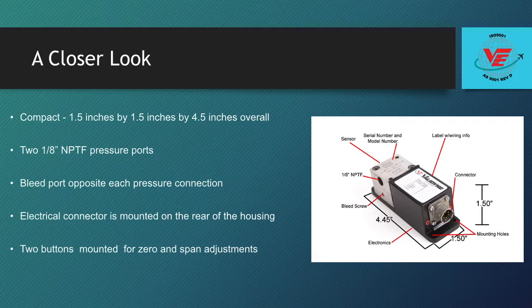The differential model shown here has two 1/8 inch pressure ports on each side of the sensor body, marked plus and minus. There also is a bleed port on the opposite side of each pressure connection to allow the bleeding of air trapped in each of the sensor cavities. The sensor body has the complete model number and serial number of the transducer etched onto the top for easy reference. A label on top of the electronics housing shows the wiring information for that particular transducer. The pin connections for power and signal are also identified.